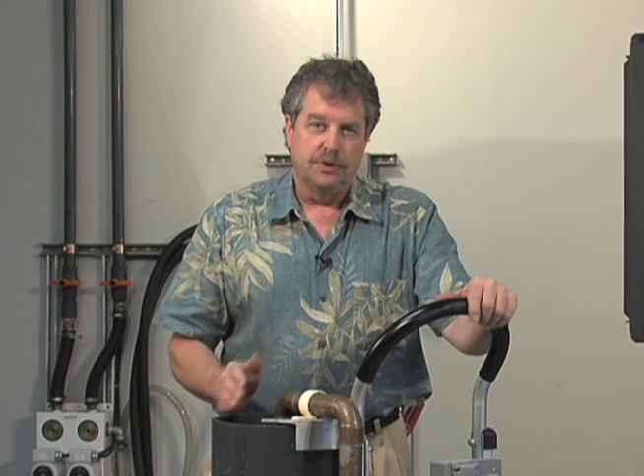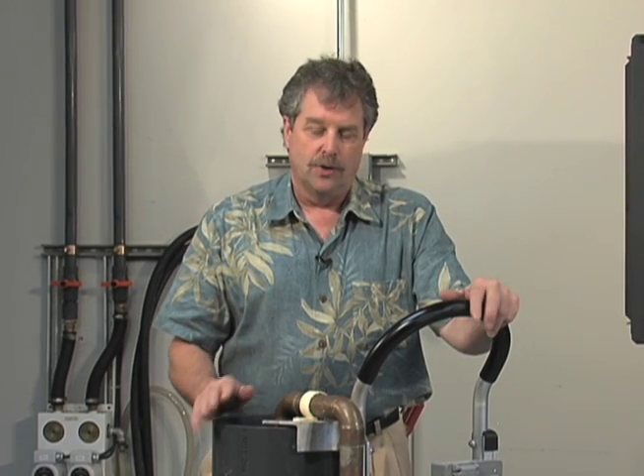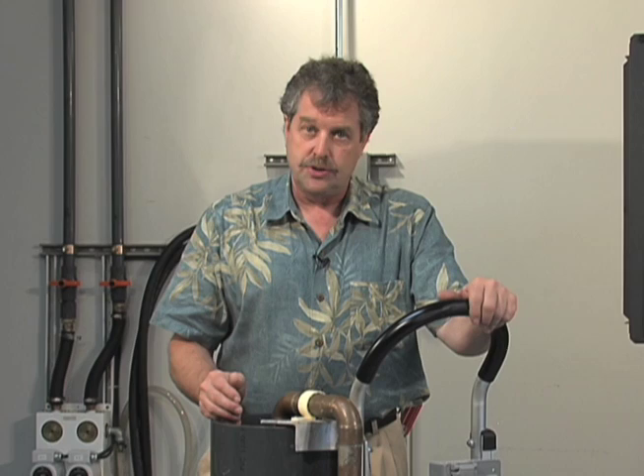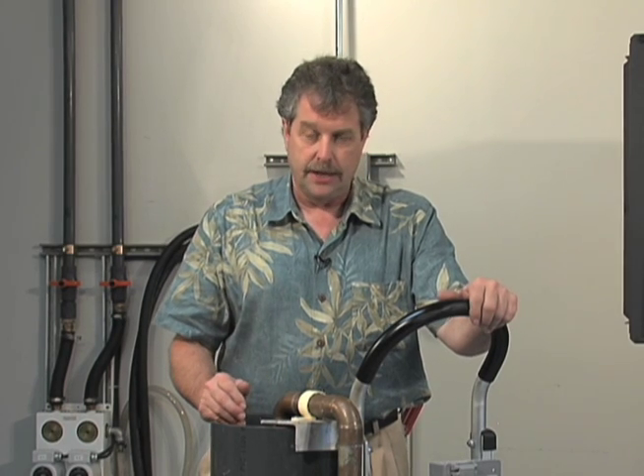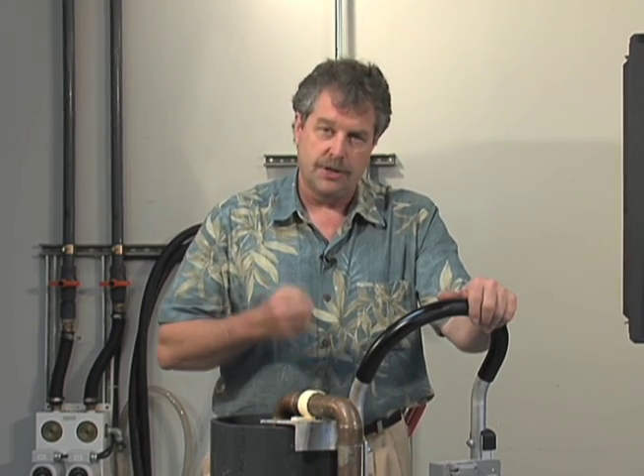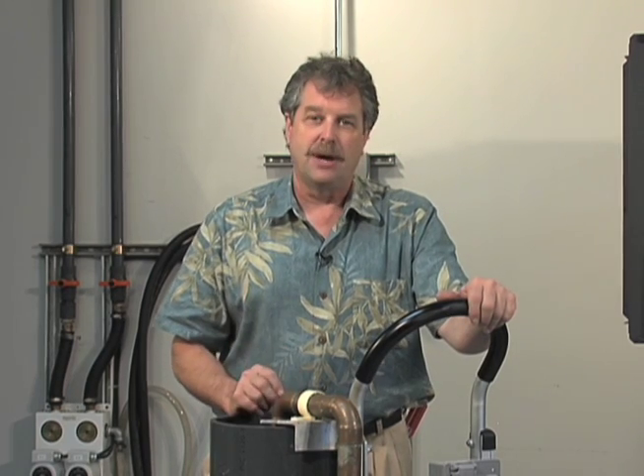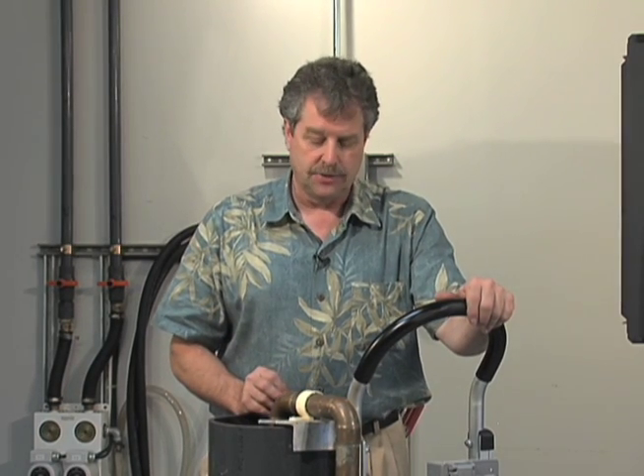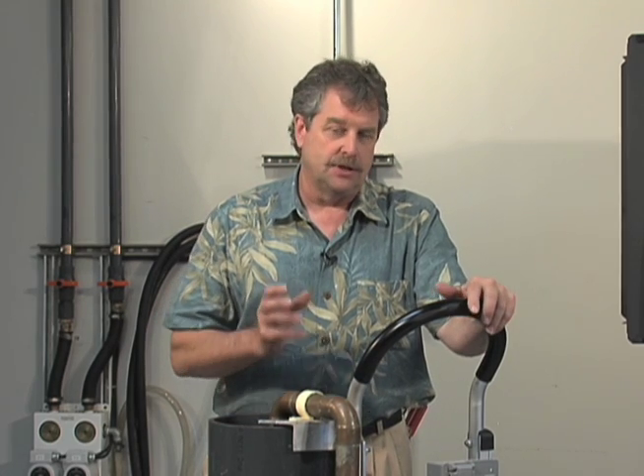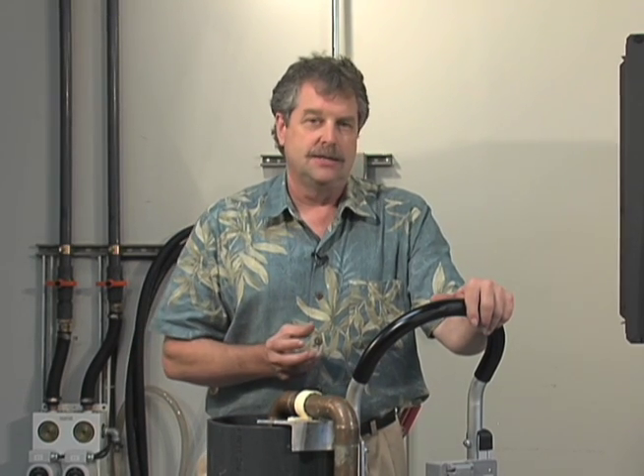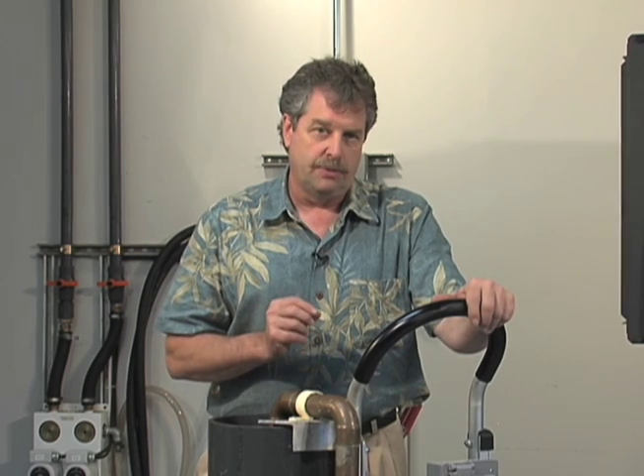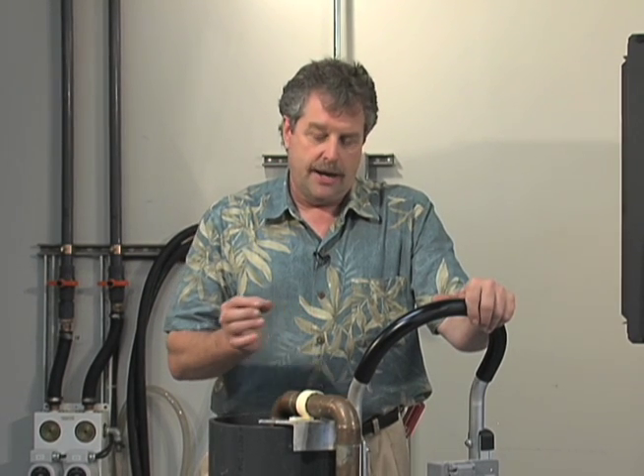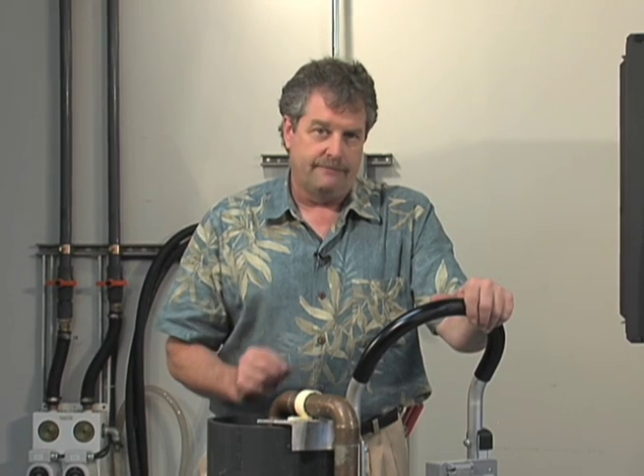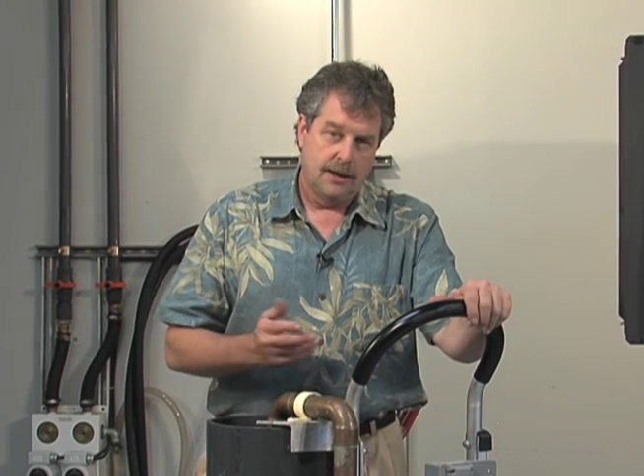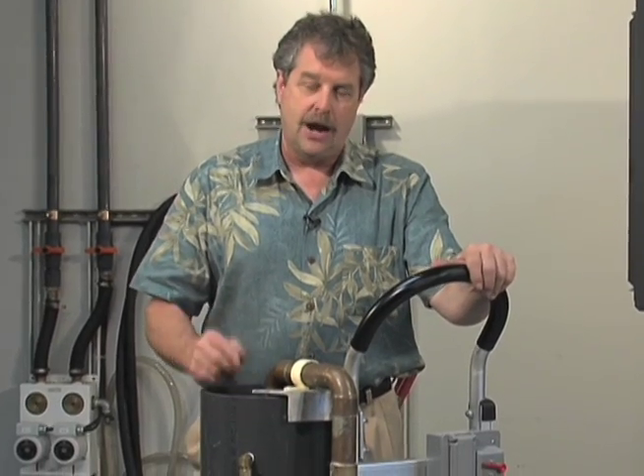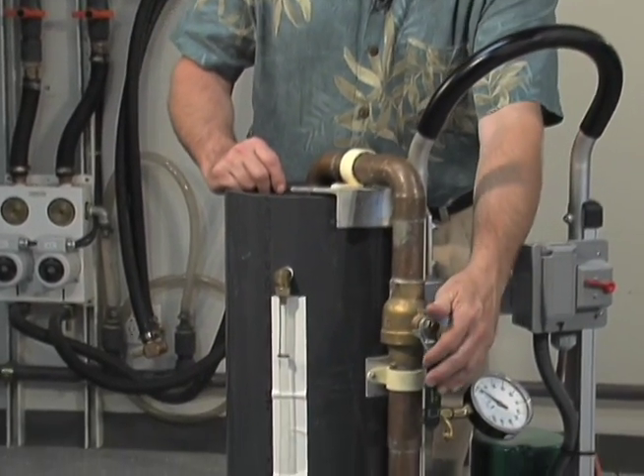So we've been circulating our fluid through the coaxial heat exchanger of the heat pump and the hose kit for some period of time. We're seeing no air returning. I've applied a number of deadheading procedures, again, getting that sweet spot of pressure, throwing that valve open to move out any air that might still be entrapped in that coaxial heat exchanger. And again, let me repeat myself that it's not a matter of the time you've spent, it's the thoroughness and the techniques that you've applied. So I've gone ahead and moved my sight glass indicator down to that fluid level, so it's time to go ahead and do a deadheading and see if we have any air still bound in our heat exchanger or hose kit.